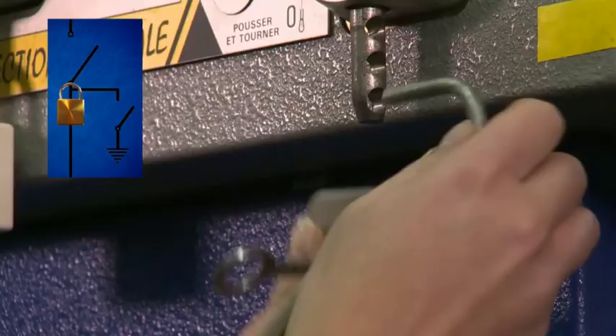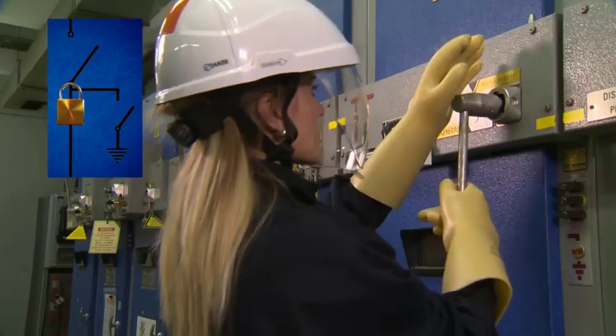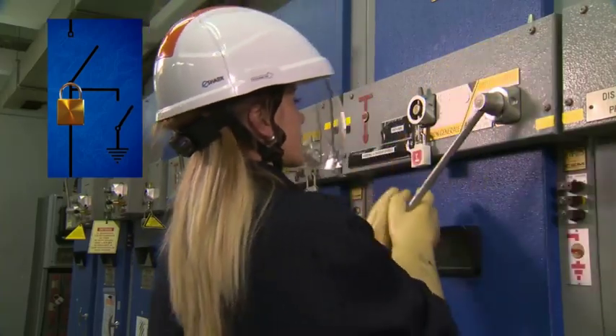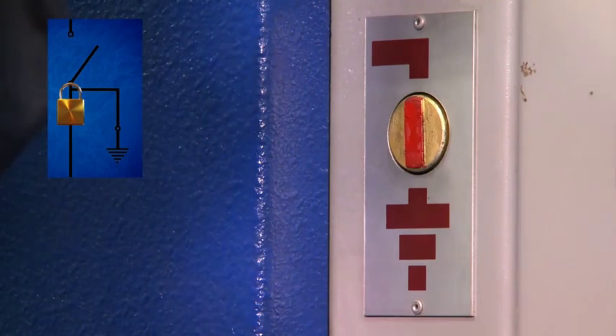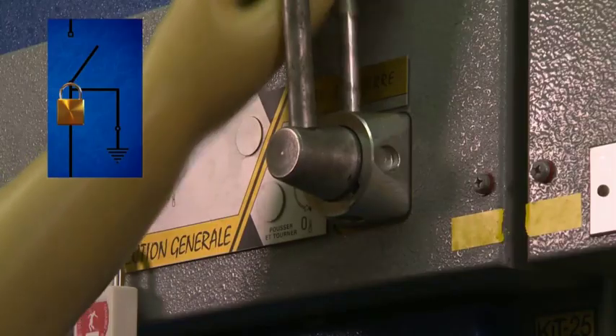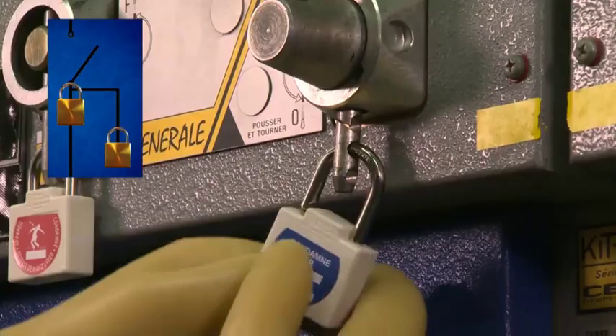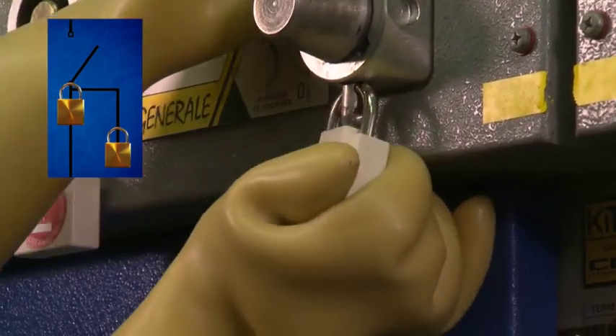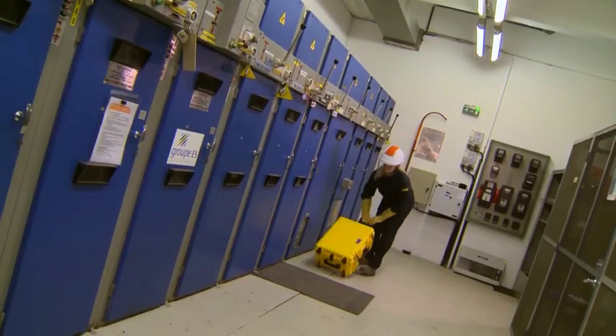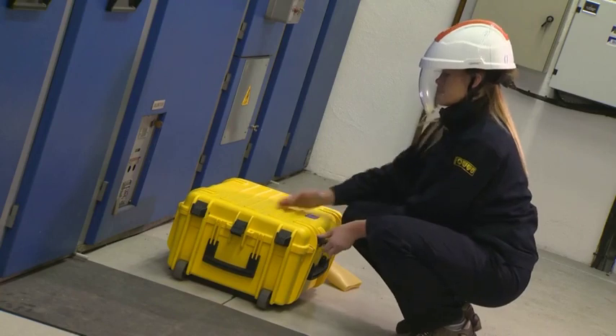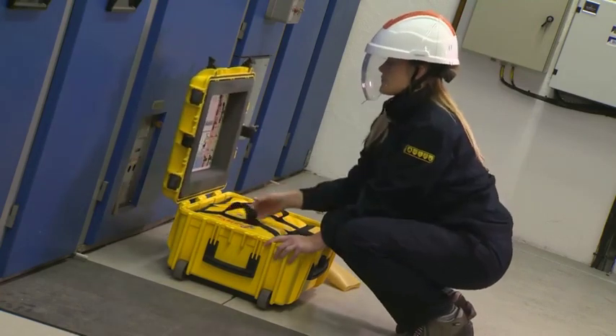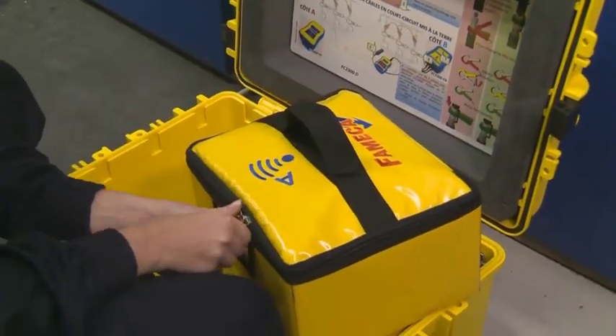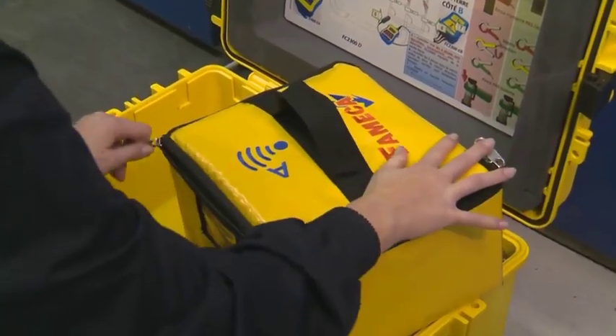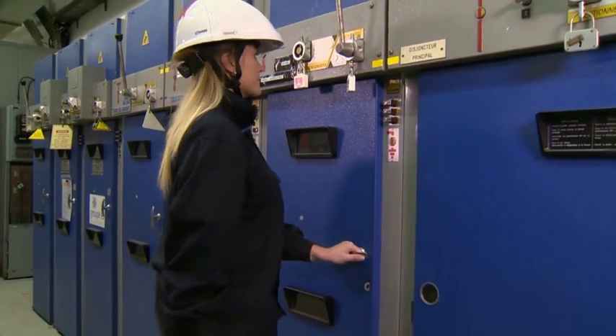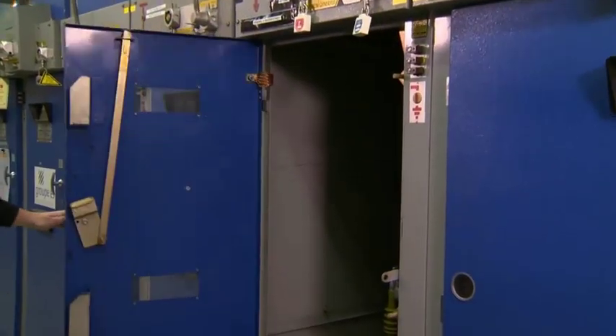We can now close the first grounding switch. Once the cable is grounded, and only at this point, can we consider it actually as de-energized. We can now install the main transmitter, or the FC2310. The special feature of this electronic identifier is that it will function with the cable being grounded and short-circuited at both of its ends.